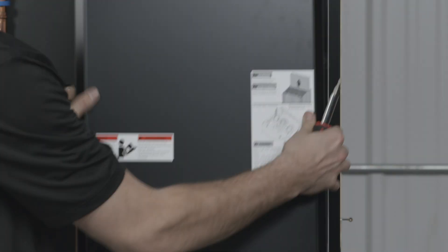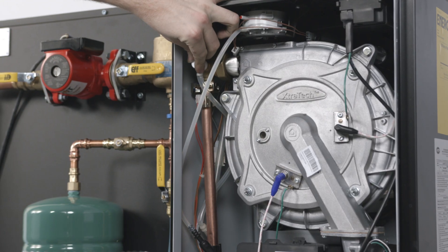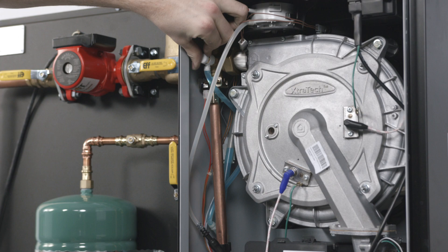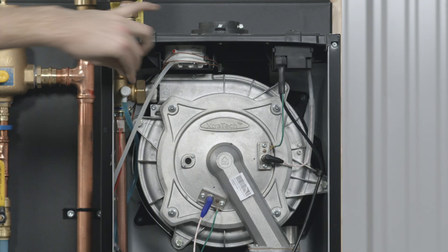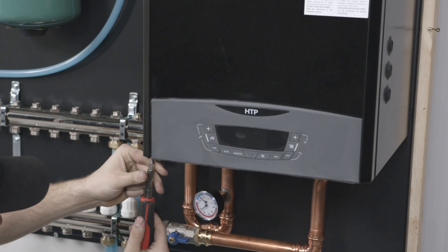Remove the boiler's front panel. Open the purge valve on the boiler until the liquid coming through has no more air bubbles. Close the valve. Replace the boiler cover.